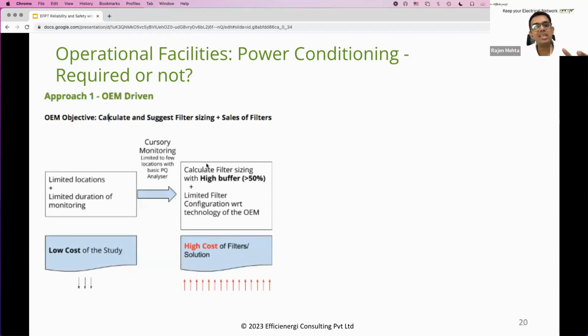The first approach we see is an OEM-driven one, where an OEM comes in, does the harmonic assessment study, and recommends to the customer that their harmonics are so-and-so, and that they need a filter of a certain size, an active filter of a certain size, and quotes the cost of the filter. This is typically what happens. We've often seen customers want a harmonic study done, so they call an OEM who manufactures filters, and that OEM does the study. The cost of the study ends up being much lower.